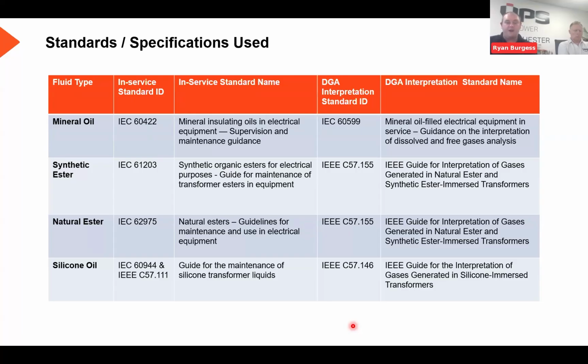Just to make a note, when it comes to sampling, the reports issued are only as good as the information that we receive and also as good as the sample. So all sampling should be done following guidelines set out in IEC 60475. And that's that on specification. Unless you've got anything to add on specifications, Andrew? No.